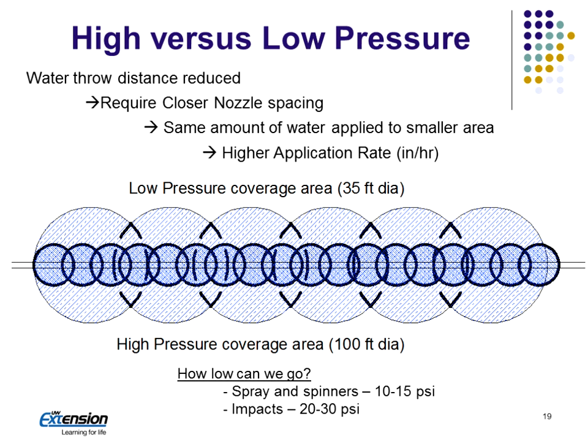To show it a little more pictorially, if we can't throw the water as far, we will need nozzles at closer spacings, and that's what this is trying to show. The large circles are high pressure, and the small circles are low pressure. Just an example. So we have the same amount of water over a smaller area. What that does is increase the instantaneous application rate. It also reduces the amount of time the water is applied to a particular spot in the field. So this is an example.